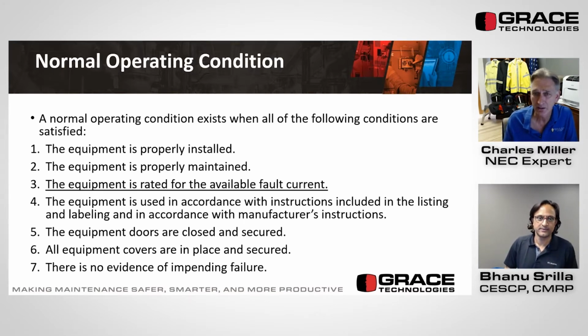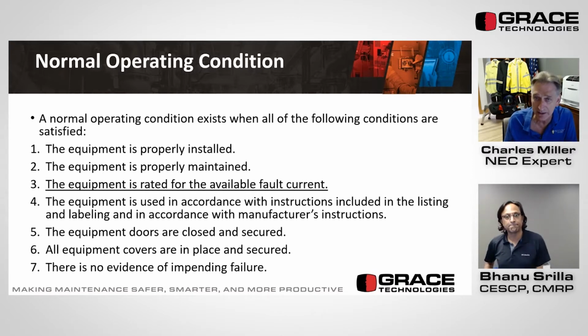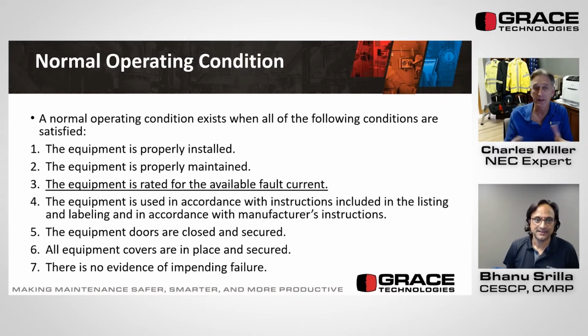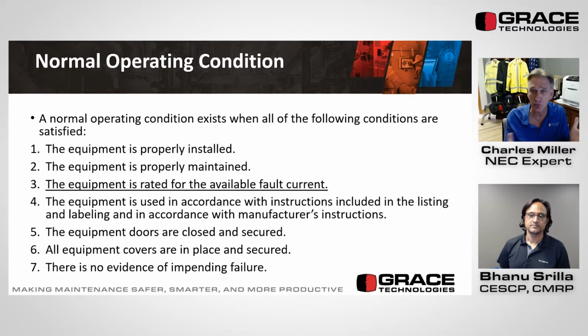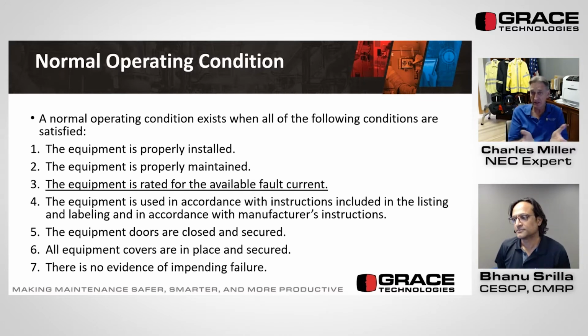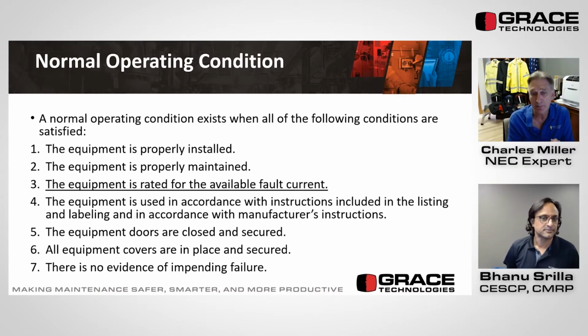Looking at this, I can see some people may say, I can't see that this is normal operating condition because I can't confirm what the available fault current is. I might be able to open the equipment up and see a label or a plaque on the front of it. If it's just a panel board, I don't think there will be. If it's switchgear, or a big switchboard, there probably will be a plaque on the front. But I don't think this will be on a panel board. So my only concern is basically that the equipment is rated for the available fault current.